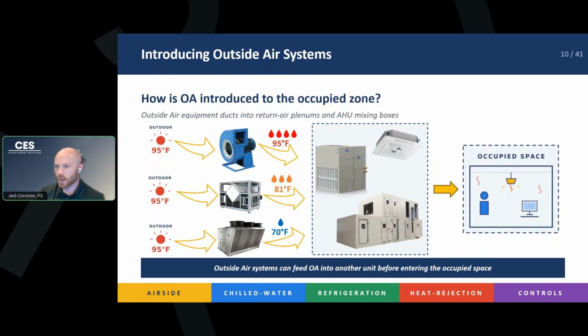A little bit more common way to do it is not to dump the outside air directly into the space with a diffuser. It's to funnel that outside air into a mechanical room or into a secondary downstream air handler that serves that individual room. In this situation, you're mixing the outside air with return air, and then it passes over a coil as it goes downstream. If you start on the left side of the screen with your outside air fan, 95-degree air doesn't change temperature or humidity as it goes over the fan blades, but maybe your indoor unit right within the middle box can handle that 95-degree wet air and deliver it into the space perfectly fine.